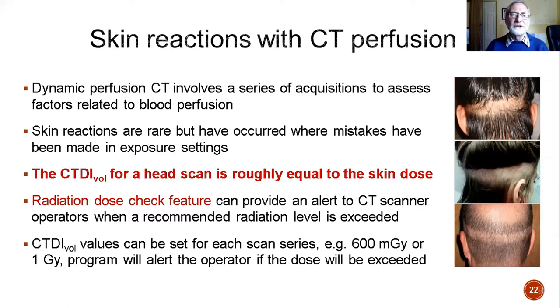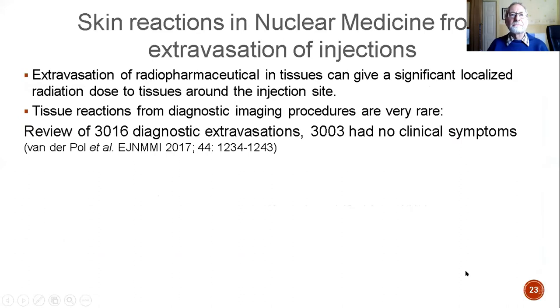A radiation dose check feature can provide an alert to the CT scanner operator when a recommended level of the CTDI vol is reached. Values can be set of 600 milligray or 1 gray, and the system programmed to alert the operator if that value is going to be exceeded.